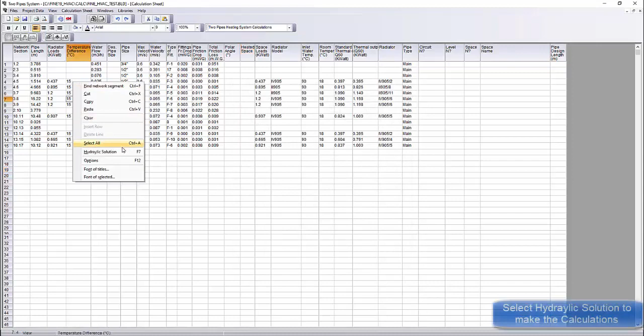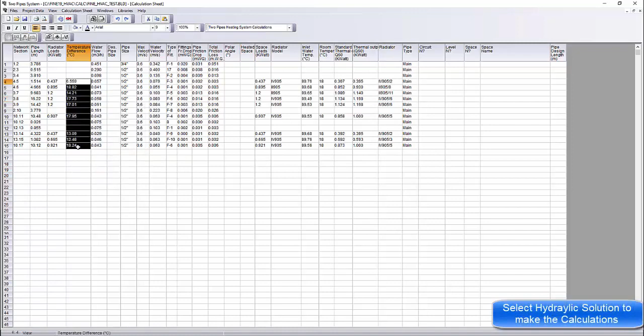With right-click on the calculation sheet, we select Hydraulic Solution. Automatically all the segments are defined with the hydraulic calculation method. The temperatures have changed due to the calculations. We need to check if any radiator has temperature drop more than 20 degrees Celsius.